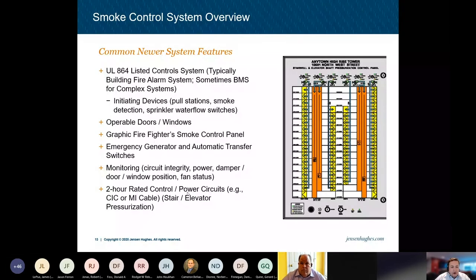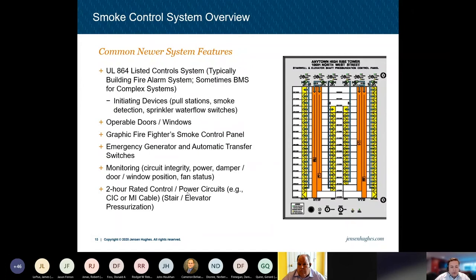You'll have, obviously, we talked about the normal and standby power. So you have an emergency generator and automatic transfer switches to back up everything. System monitoring, so circuit integrity, monitoring power, damper and door position, and also fan status. And then you'll have 2-hour rated control and power circuits. So that could either be CIC cable or MI cable, or it's the actual physical circuits installed in 2-hour construction or outside the building. And that's when you have a stair and elevator pressurization systems.